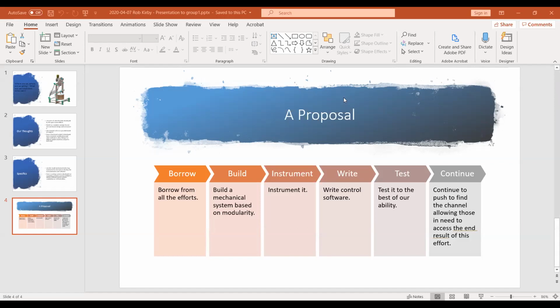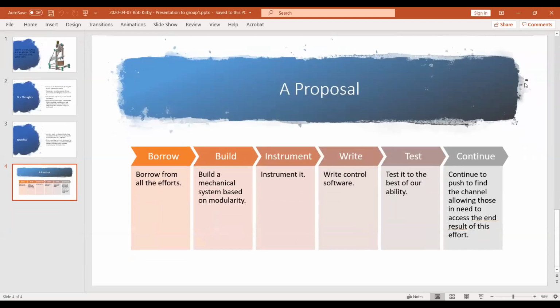We want the mechanical system to be modular, such that if you want to change the ambu bag out, not a problem. When I say that, I'm talking about the oxygen mixing and a lot of the other features, the plumbing, if you would, that could be uploaded onto a different source of air, whether it be the ambu bag or a bellows or a piston. We looked at pneumatics as well.